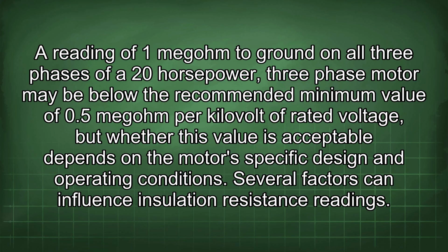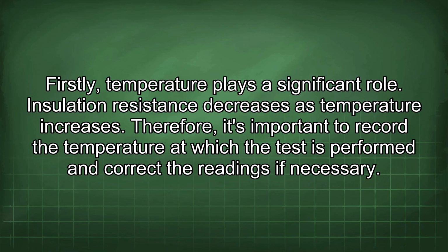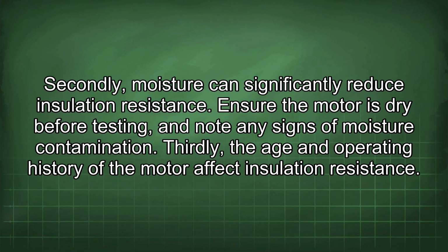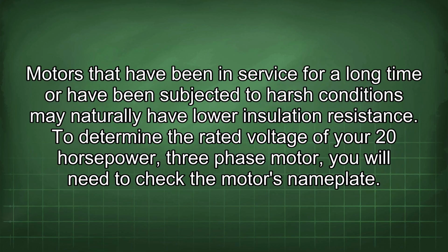Several factors can influence insulation resistance readings. Firstly, temperature plays a significant role. Insulation resistance decreases as temperature increases. Therefore, it's important to record the temperature at which the test is performed and correct the readings if necessary. Secondly, moisture can significantly reduce insulation resistance. Ensure the motor is dry before testing and note any signs of moisture contamination. Thirdly, the age and operating history of the motor affect insulation resistance. Motors that have been in service for a long time or have been subjected to harsh conditions may naturally have lower insulation resistance.